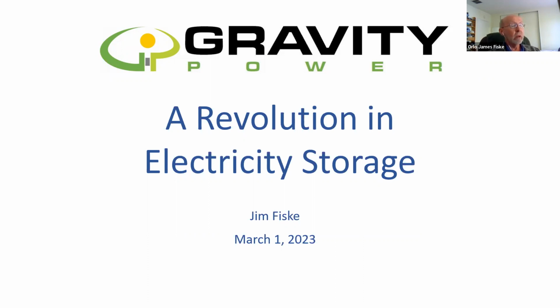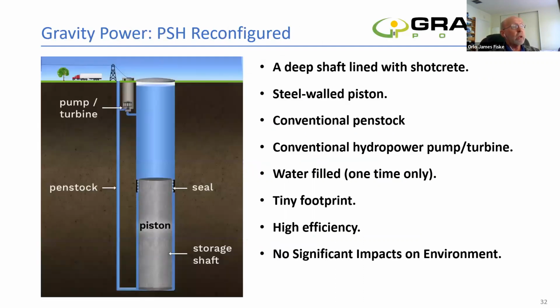Next slide please. Our solution is to build a new type of pumped storage hydro, which starts with a conventional powerhouse, totally conventional pumped hydro powerhouse. Adjacent to the powerhouse, we excavate a very deep shaft. In that shaft, we put a steel-lined piston made mostly of rock and concrete. We have a conventional penstock connecting the powerhouse and the shaft, and fill the whole thing with water.